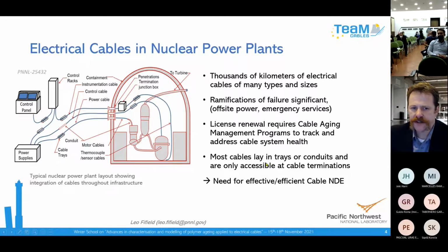Now, a challenge is that most cables are not easily accessible. They go through concrete walls. They're up on cable trays. They're not easily accessible, and often you can only access the cables at the terminations to test them. So that's a challenge with testing all the cables in the plant. There are many cables, many more than can be tested every outage.